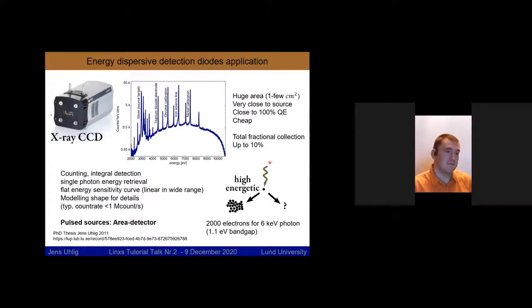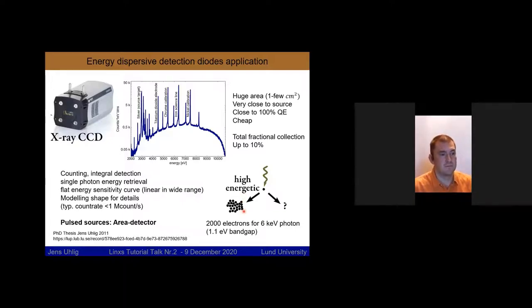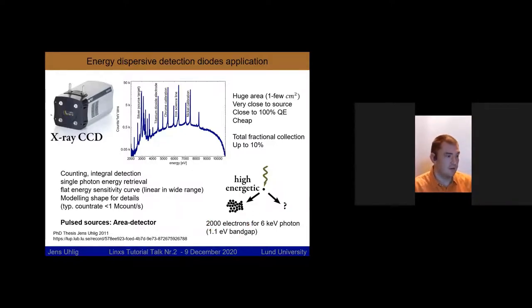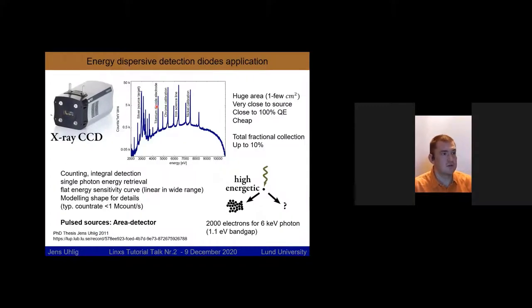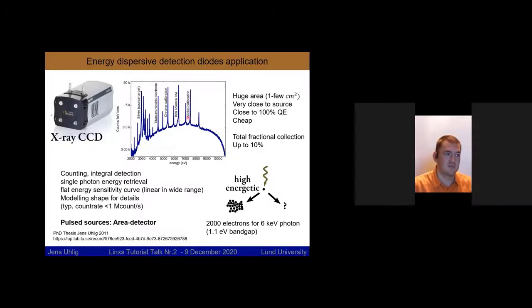The challenge is that the energy resolution from these cascade-based detectors is limited by the number of electrons produced — about 2000 electrons for a 6 keV photon in silicon due to the band gap. This gives resolutions of about 100 eV at 6 keV, which is sufficient for XRF and for analyzing your source spectrum, but not enough for high-resolution science.